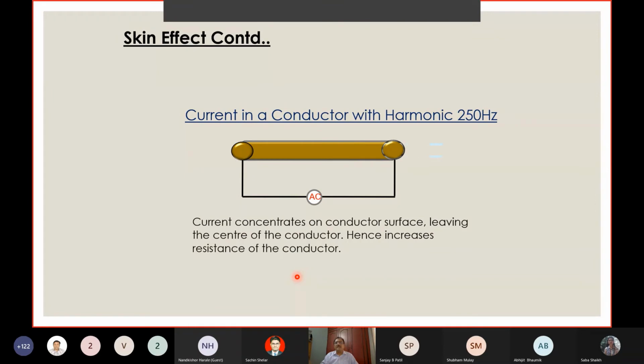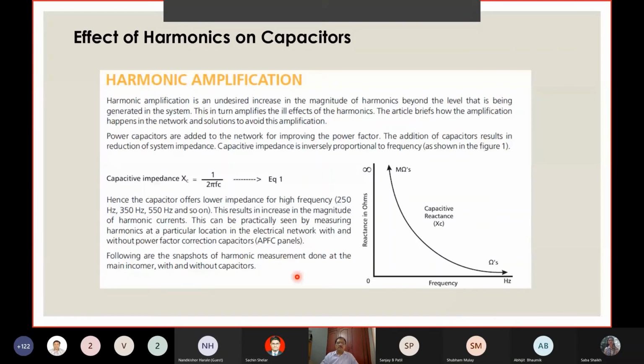So we talked about upsizing. Here, the upsizing alone will not help us to reduce the I2R losses. Now, the worst enemy for resistance, as you all know, is also temperature. So if the temperature is going to go up, the resistance is going to go up. We are talking about upsizing as an opportunity for energy saving, but that alone is not sufficient. So wherever we use devices operated through VFDs or SMPS, we should use metal braided cables or cables recommended by the manufacturers. Ordinary PVC or XLPE cables are not sufficient. So skin effect is one effect which causes a lot of distribution losses. Now I spoke about capacitors, plain capacitors amplifying harmonics.